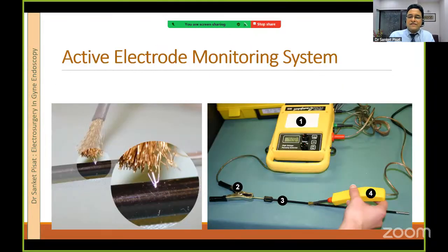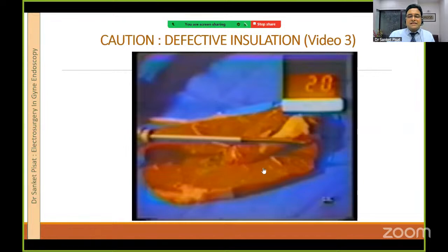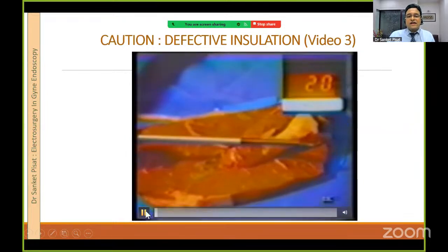So this is the active electrode monitoring system. It's not actually used that much in practice, but this is like a brush which is run over the surface of the instrument, and any spike caused by current leakage is noted by the instrument immediately, and you know this instrument has to go for repairs or for replacement. This is again a video of defective insulation.